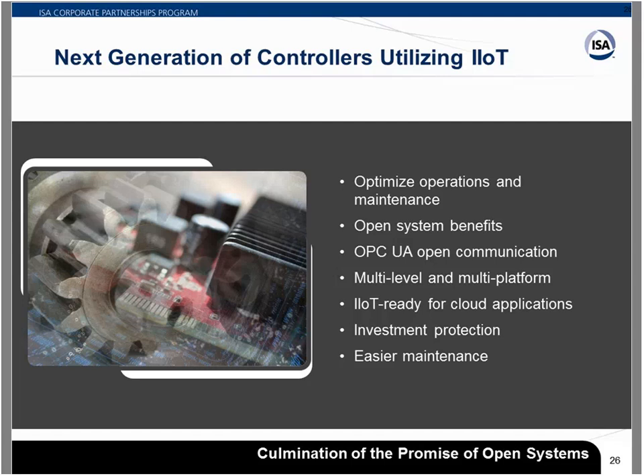With these IIoT connected or capable controllers, you're now able to reach directly down from your SCADA or DCS system, not just on a point-by-point basis, but OPC UA actually supports full objects, that data model type stuff I was talking about. For example, a PID loop typically has 25 to 50 subpoints, subtags associated with it. Now that can become a small data model that gets matched up at the SCADA level with something like a PID faceplate. DCS has had this for a while; now you're going to see this faceplate-to-SCADA-HMI-server-level mapping become possible through some of these protocols.